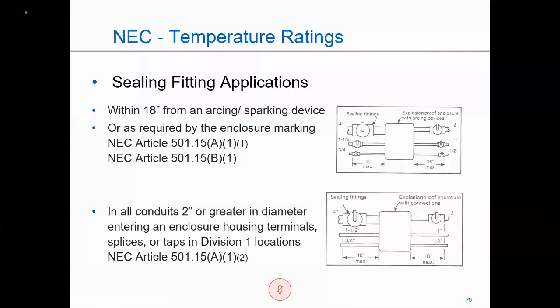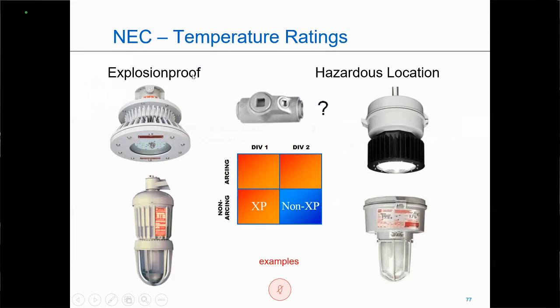Is a junction box normally going to heat up like that, where it can exceed 80% of the auto ignition temperature of a particular gas or vapor? I can't imagine. I've never seen where it has happened. So at least not in my experience. That doesn't mean it hasn't. So that's where I would be 2 inches and larger. But what could be a product that could heat up? Luminaire. So in this particular case, if this luminaire could heat up and exceed 80% of that auto ignition temperature, then I would have to seal all entries, not just 2 inches or larger.